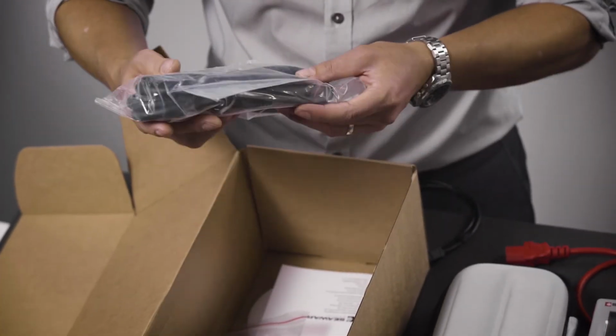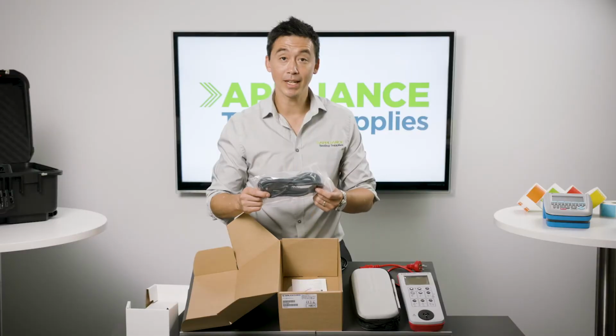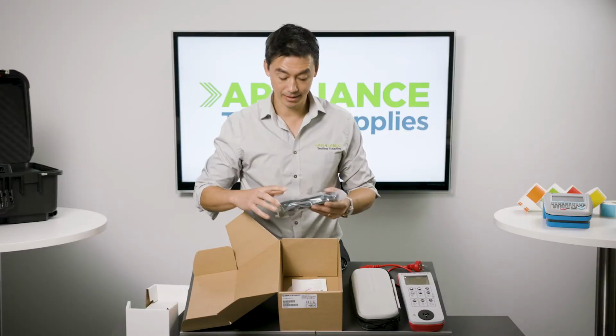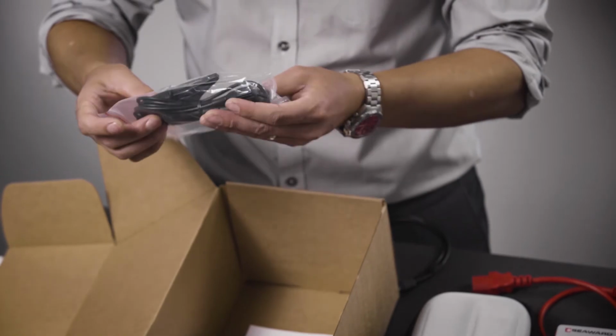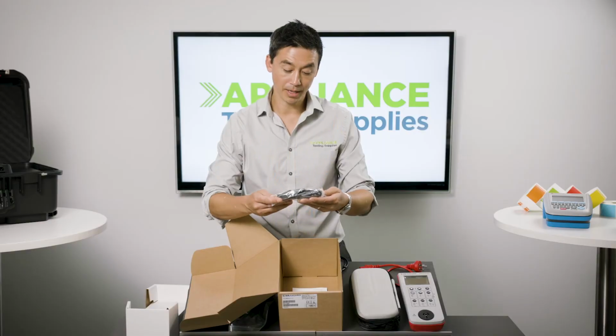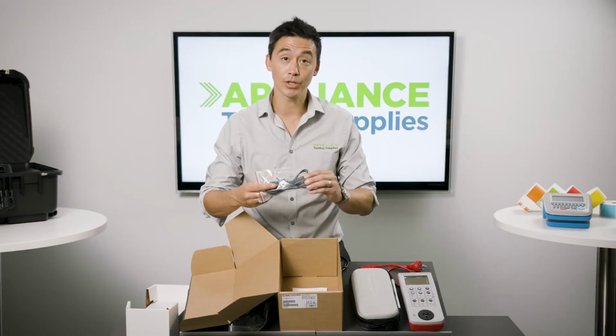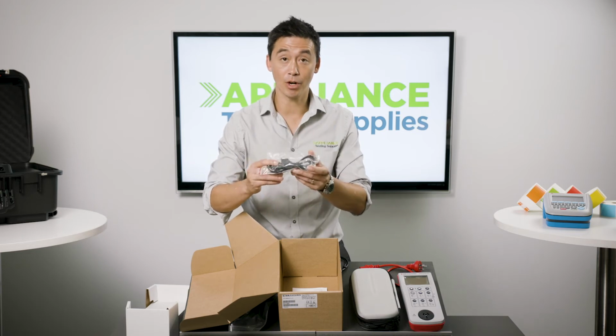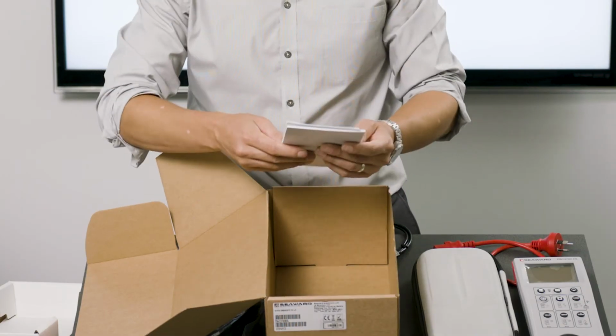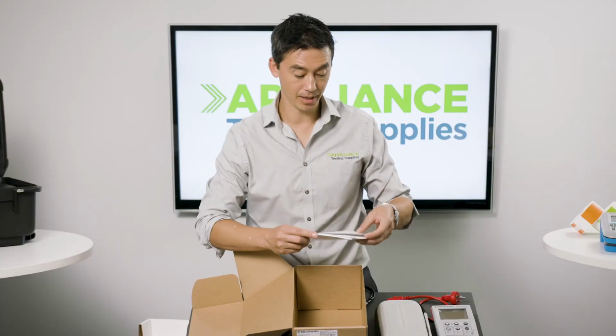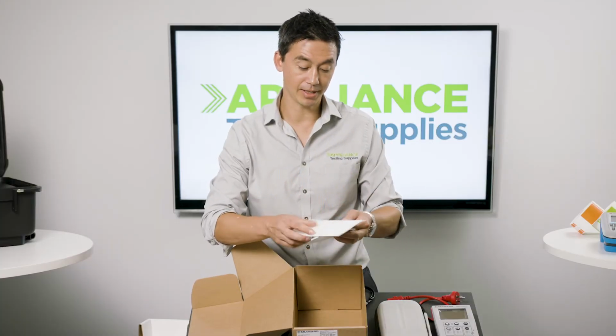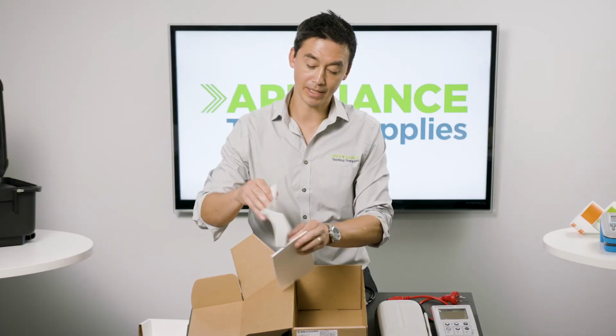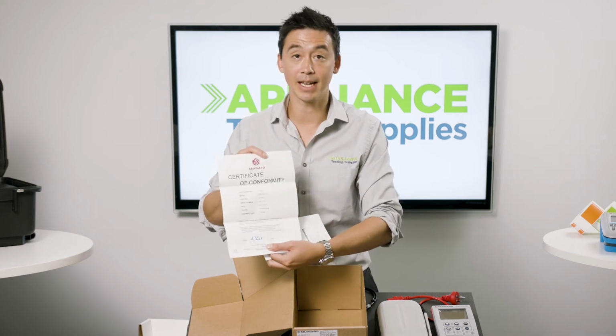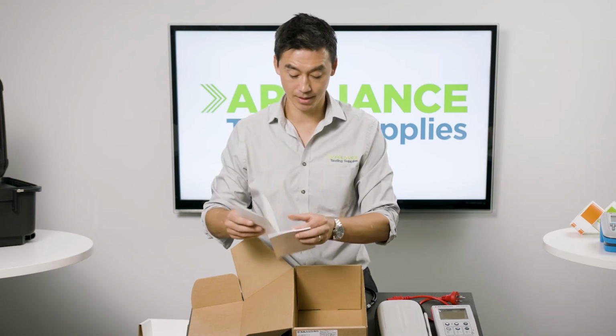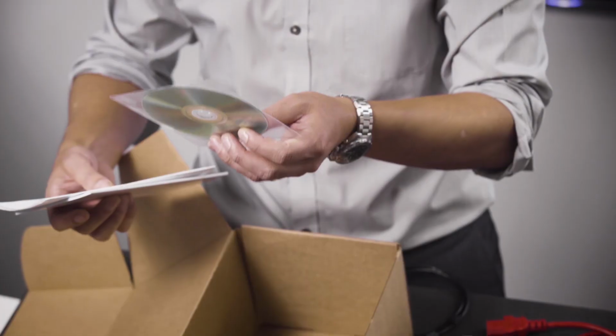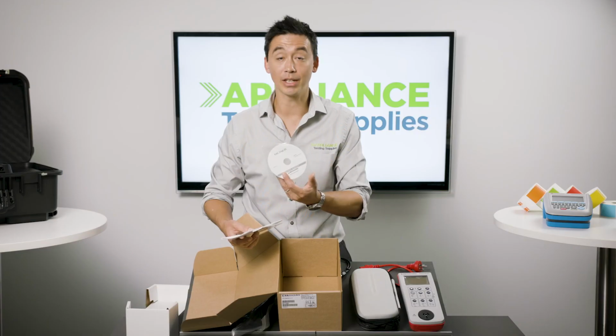The main supply lead, so when you're running leakage current or run testing, you'll need this test lead. We have a crocodile clip and probe set for your earth return. So that's interchangeable between the probe and the clip. We have the tester's instructions, and inside the instructions we have a certificate of conformity, pretty much stating that the tester meets the Australian standards as per the manufacturer's requirements. And lastly, there is a support CD with the downloading software in there too.